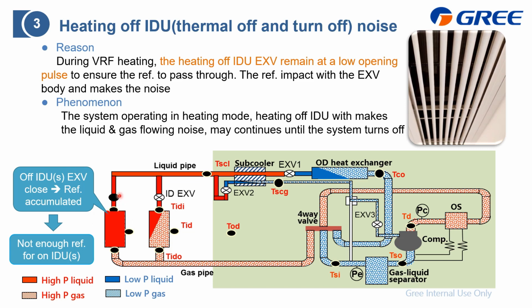So in conclusion, even when it is turned off, we still keep this indoor unit EXV at a low pulse to make sure the refrigerant still goes through it. So we know why we need to keep it open, and also just because it is open, the refrigerant impacts with this EXV body and makes the noise.